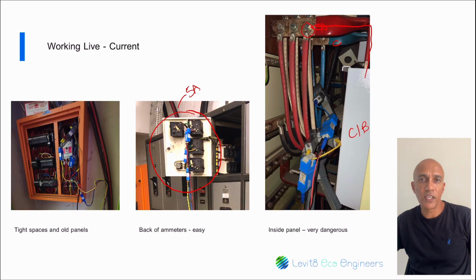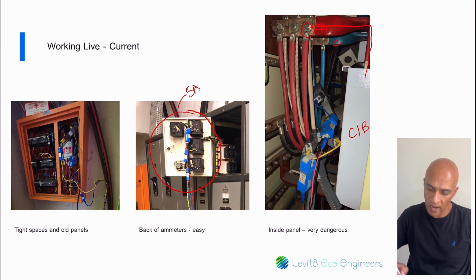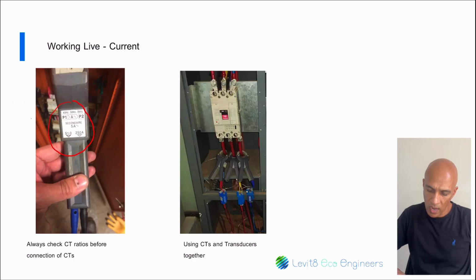Now in my case, I have an instrument that works with the 5 amp 1 volt transducer. I also have variable CT clamps which can be adjusted to 250, 500 or 1000 to 5 amps. Now here's a picture of the kind of clamp-on CT that I have. And here at the bottom, on the one side, I have S1, then I have 250 amps here, and on the other side, the other arm leg of the CT, I have a 500 and I have 1000 amp.